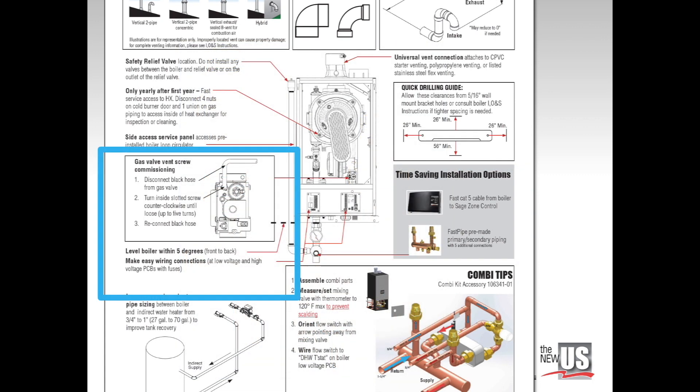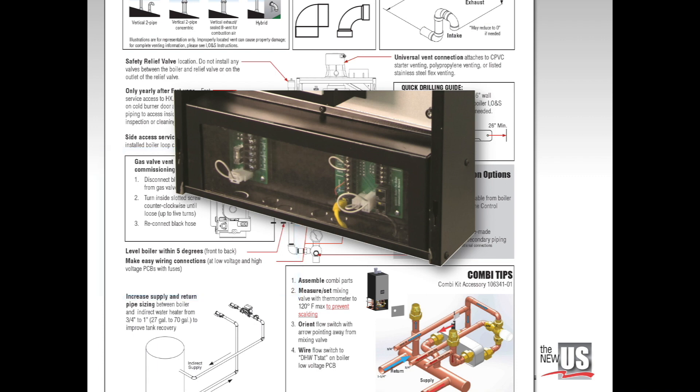Here are other quick tips from expert K2 installers: level the boiler within five degrees. Always check the vent screw under the hose — if present, open counterclockwise before reconnecting the hose. High and low voltage connections are always separated between two printed circuit boards. Ignore the combi tips at the bottom right; this accessory was discontinued after US Boiler introduced its dedicated combi boiler.